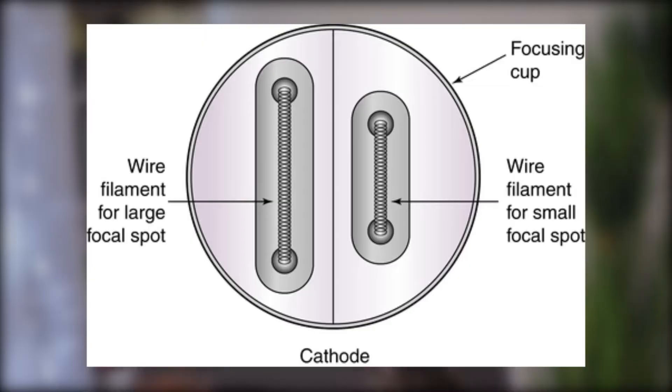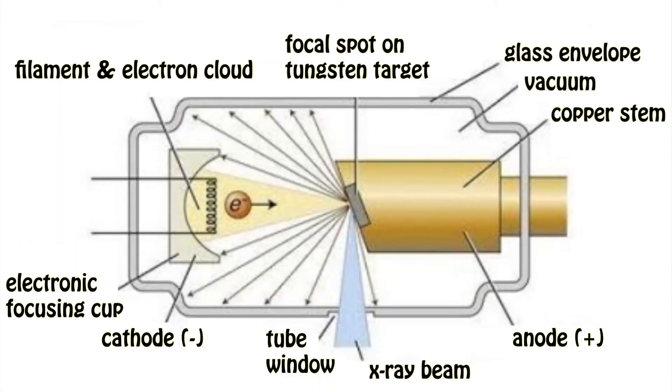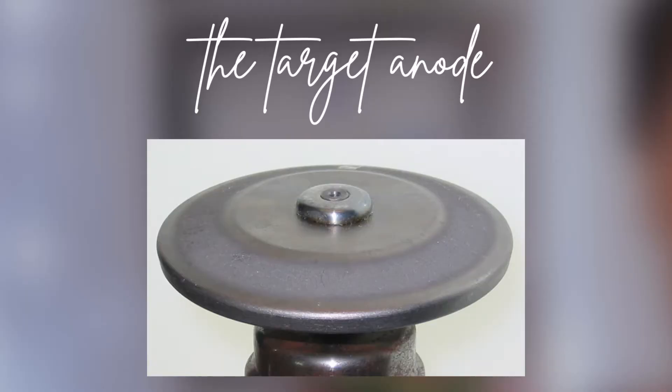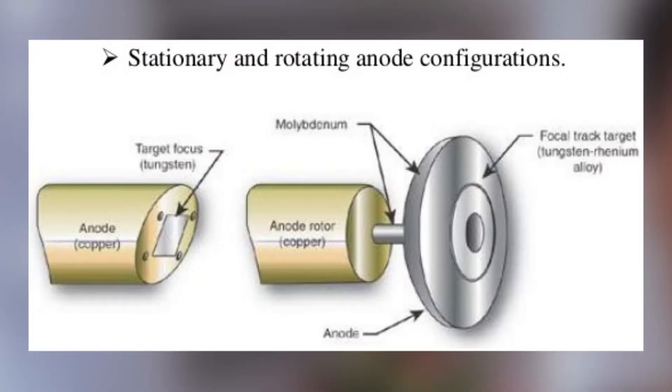The size of the filament is related to the size of the focal spot, and in many cases cathodes have two sizes — broad and fine focus. The filament is housed within the focusing cup. The target is at the anode, the positive side of the tube, and it is where electrons strike to come to that sudden stop and create x-ray photons. The target is also made of tungsten for the same reasons. Rhenium is added to the target to prevent cracking and melting at high temperatures.